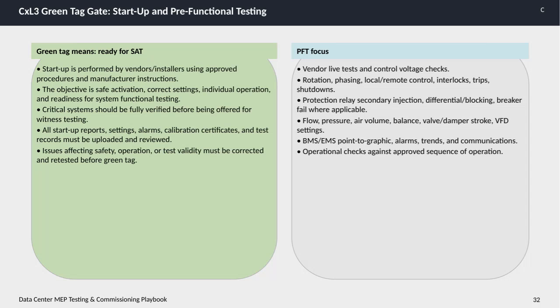On this slide, we're focusing on the CxL3 Green Tag gate, which marks the stage of startup and pre-functional testing in the commissioning process. The green tag signifies that the system is ready for the Site Acceptance Test, or SAT. Startup is carried out by the vendors or installers following approved procedures and the manufacturer's instructions. The goal here is to ensure a safe activation of the equipment, the correct configuration of settings, individual system operation, and overall readiness for the subsequent functional testing phase.